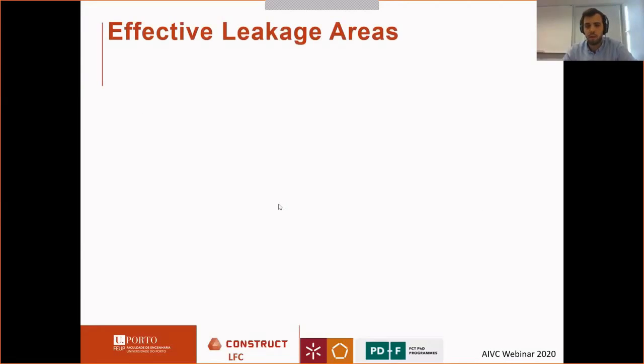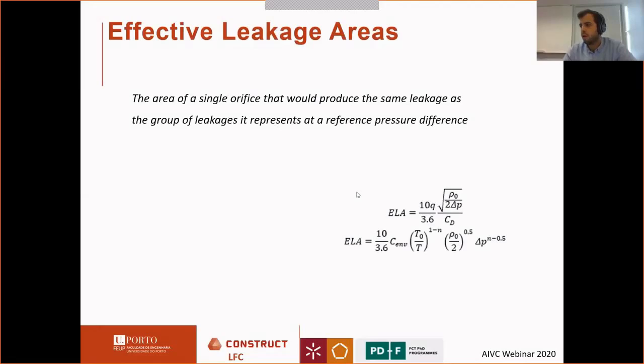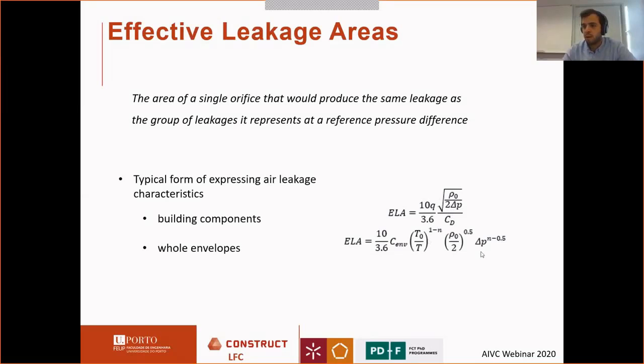Effective leakage areas are obtained from the treatment of air tightness measurements. It represents the area of a single orifice that produces the same leakage as a group of leakages at the reference pressure difference. It is dependent on the airflow, the pressure difference, the temperature or air density, and the discharge coefficient. Normally it is the form of expressing leakage characteristics of building components or even whole envelopes.